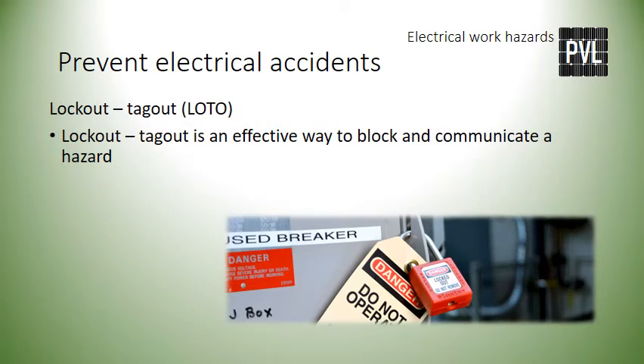Lockout/Tagout, sometimes called LOTO, is an effective way to block and, at the same time, communicate hazards. During lockout, a padlock or similar locking device is placed on a power source, switch, or circuit breaker before working on that piece of equipment. This is done to prevent someone from energizing the equipment. Your name, photograph, worker identification number, and telephone number are often required to be placed on the label that goes on the lockout device.